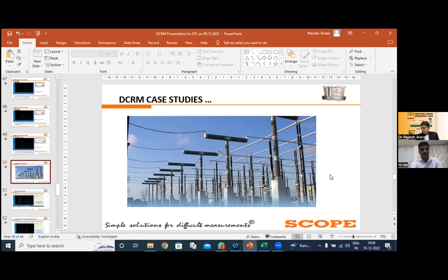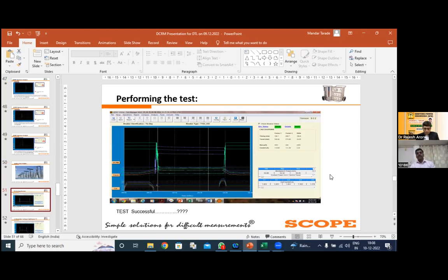So this is actually the performing test. Depending on the number of channels and the number of breaks available on your CB: if it is below 220 kV, then we have 3 breaks, R pole, Y pole, B pole, each having an individual, single break. If you have 400 kV, then each pole has 2 breaks. And accordingly, we do the analysis. In the case of 765 kV, each pole has 4 breaks, and accordingly we do the analysis or take the signatures.